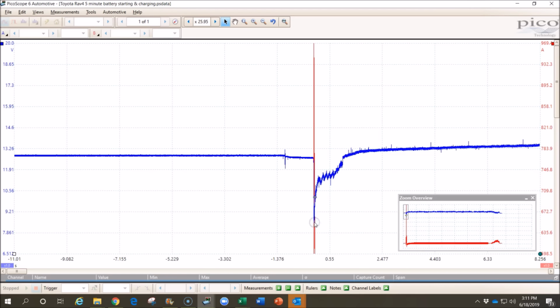That's a battery load test. We loaded the battery and tested the voltage while the current was flowing. The minimum voltage that's acceptable on this test is 8.0 volts, so this battery at 8.5 passes the test.